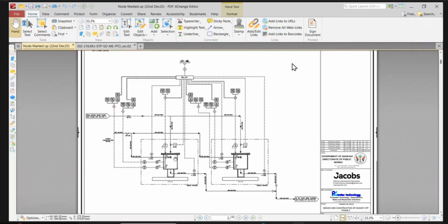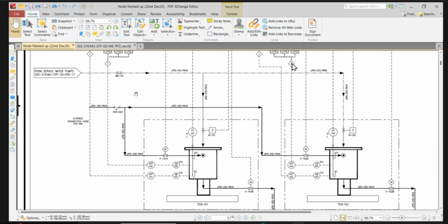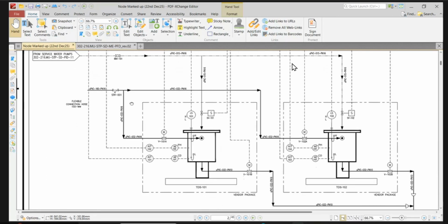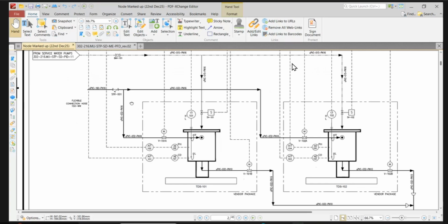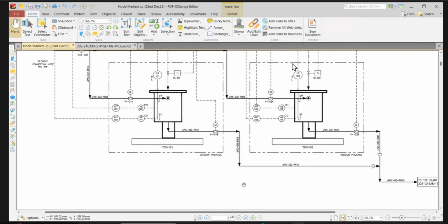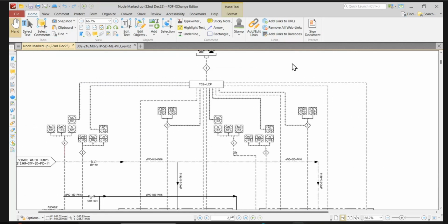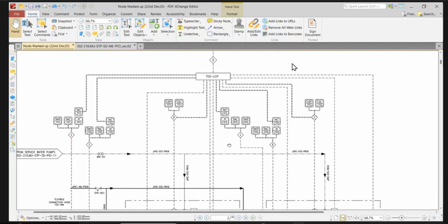You will take a sample from the tanker. There is a quick coupling. Yeah, on the left side, there's a quick coupling there. So you will take the sample to one of these units, and you have pH and conductivity. If you can see, there is a sensor down, pH and conductivity. So if it's coming high, you also have an alarm at the top. There is an alarm coming, so it will give you an indication with a red color that it is not allowed.